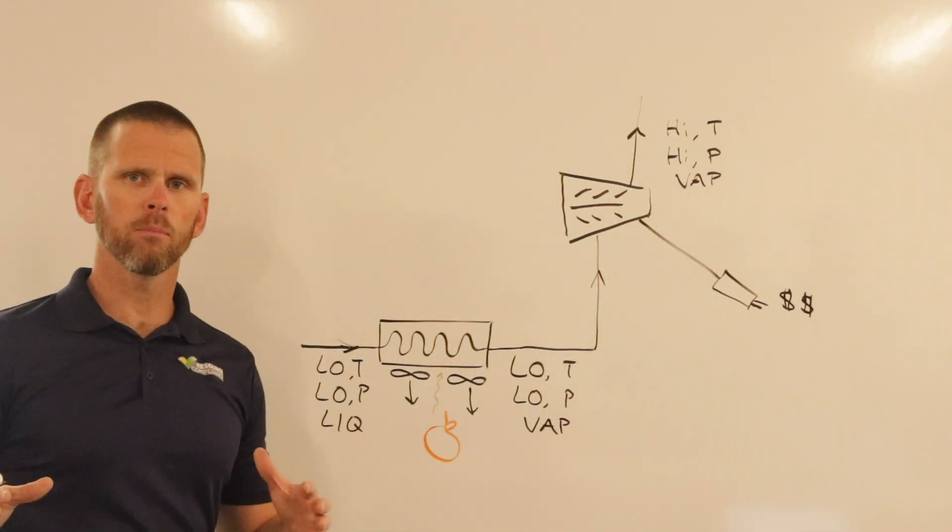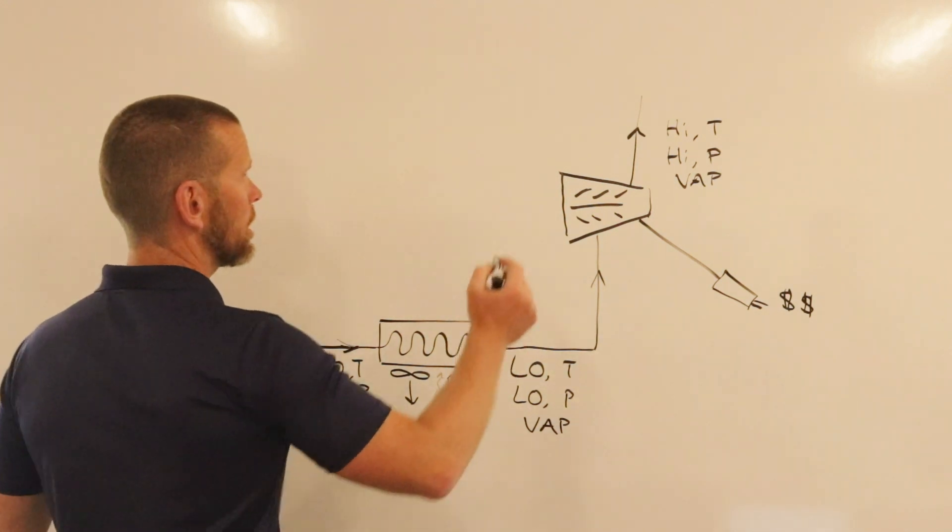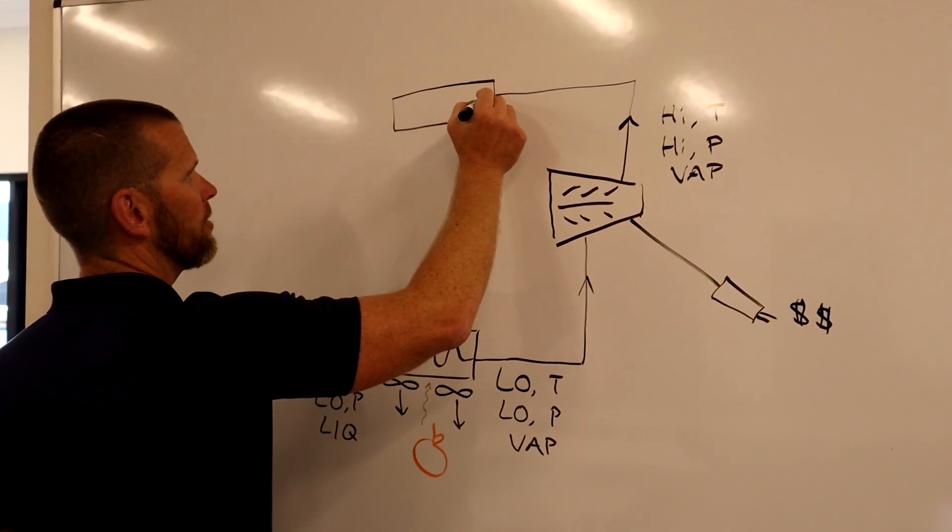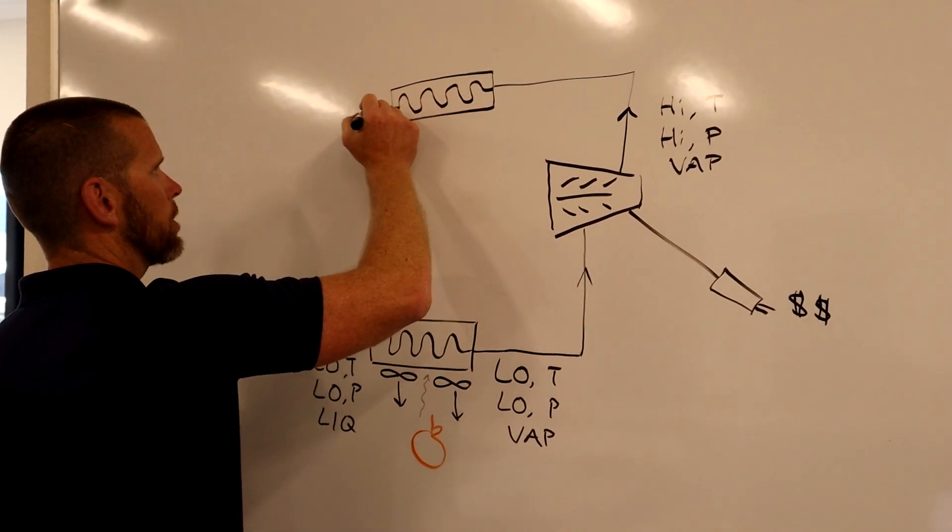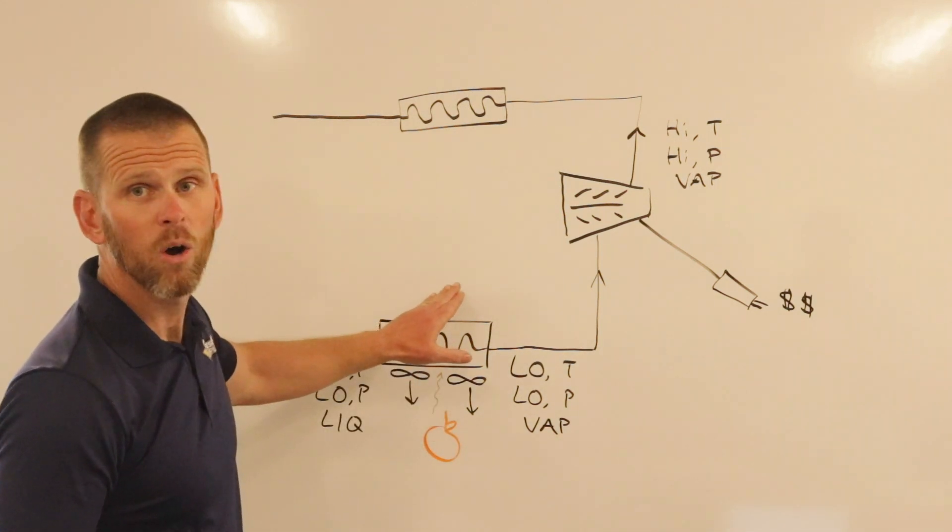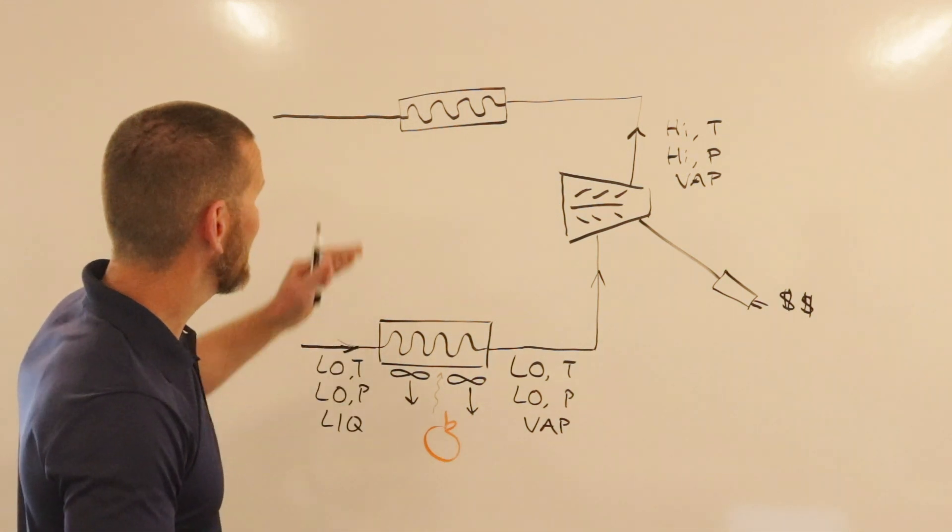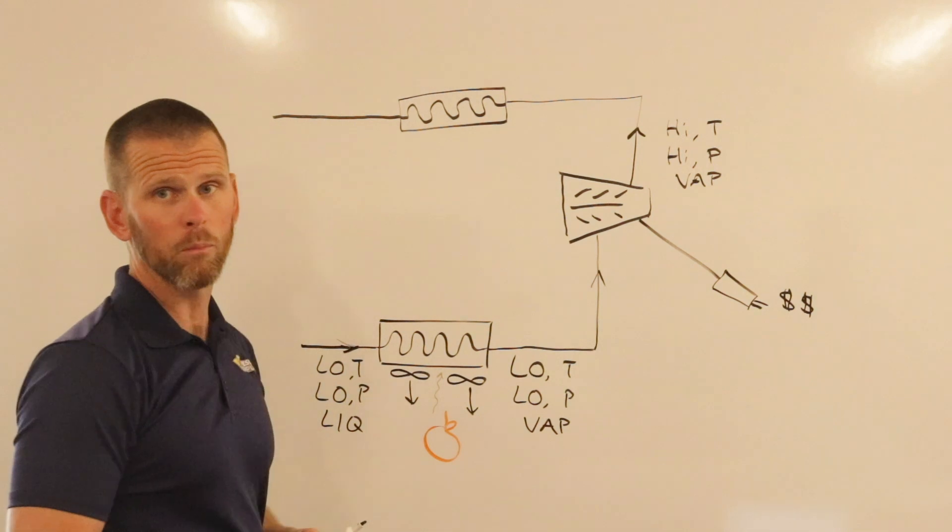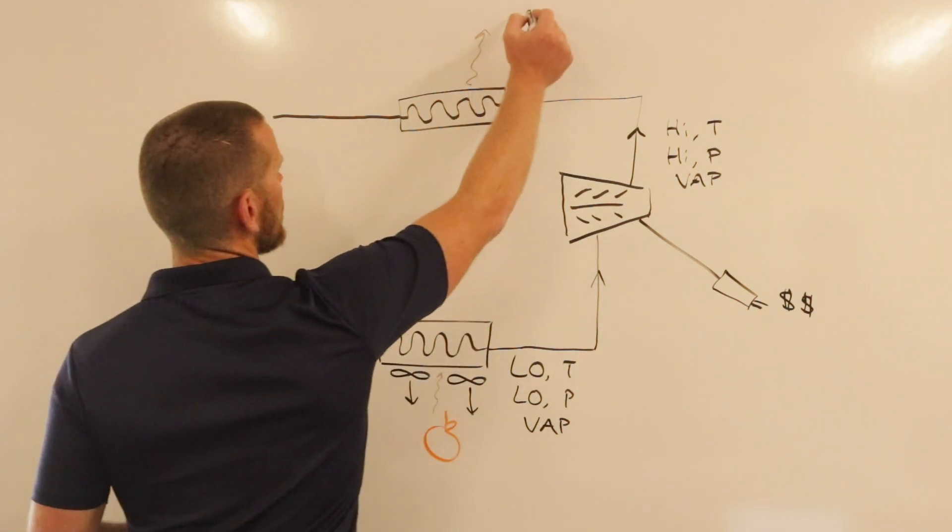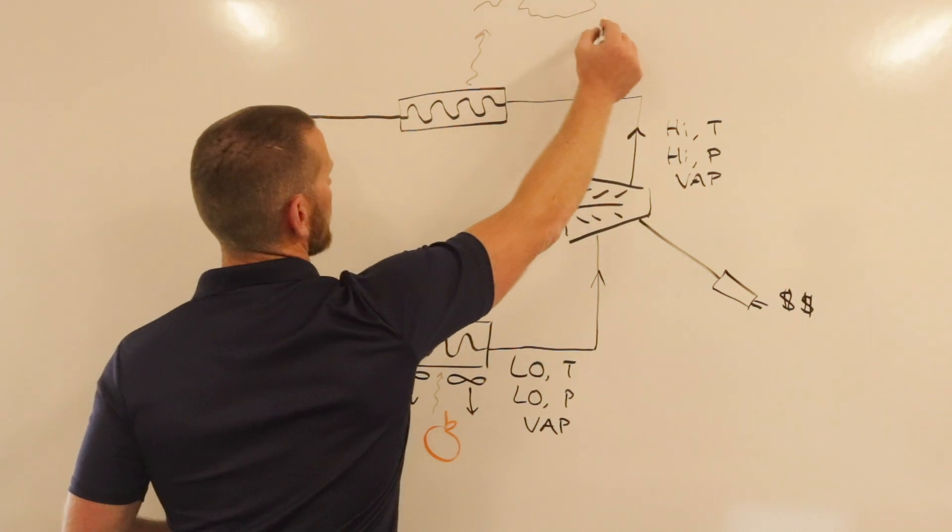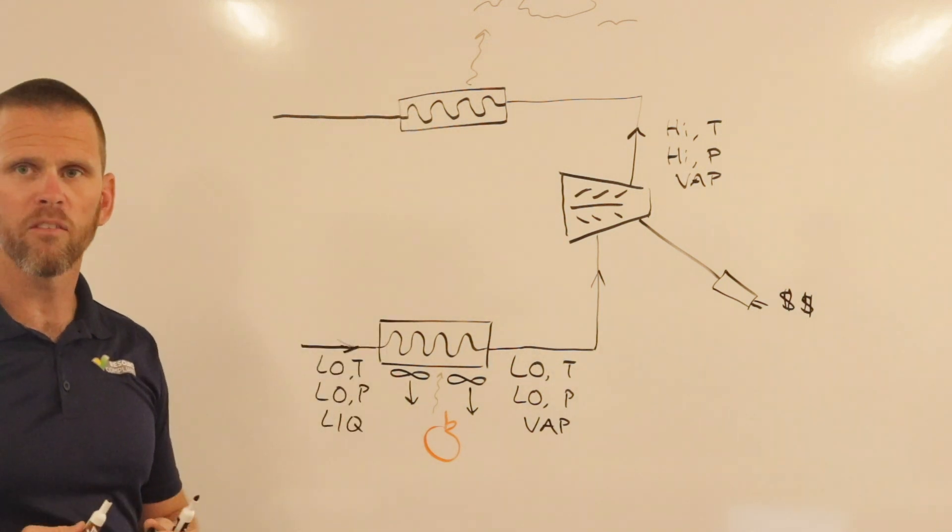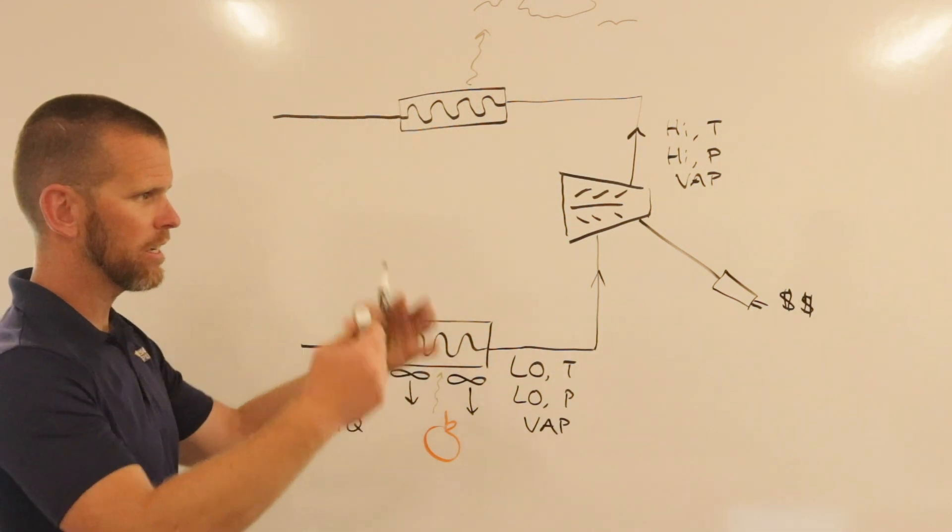We leave the compressor as high temperature, high pressure vapor. What do we do with that? We send it through a second heat exchanger called a condenser. Just like the evaporator, this is exchanging heat. The major difference is the direction of heat transfer. In the evaporator, heat from our orange was absorbed into the ammonia. At the condenser, we're not absorbing heat - we're rejecting it. Where do we reject the heat? In most cases, we reject it to atmosphere. We're sending that heat to a place where it can do no harm, typically the ambient conditions outside.